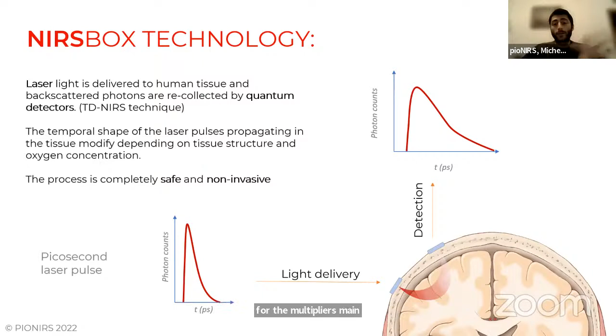As Jose was mentioning before, we are measuring tissue oxygenation and hemodynamic parameters in quite a different way. So we developed time domain near-infrared devices, and here, if you can see it, is a picture of the device. It's a bit smaller than a shoebox. What we do is inject picosecond laser pulses in the near infrared region, very short laser pulses, and we detect them using quantum detectors, mainly silicon photomultipliers. By looking at the changes in the shape of the pulse, we're able to detect the concentration of oxygenated and deoxygenated hemoglobin inside the tissue.